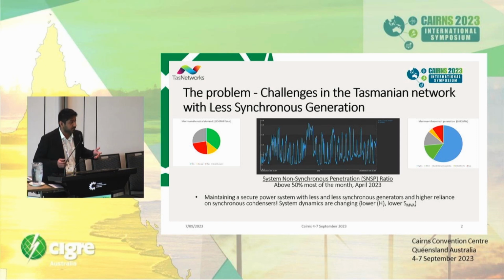So basically, if we encounter a fault, we need to see if a wind generator is injecting reactive current during that time, or whether it gets desynchronized from our network. So it's really important to get that visibility, and the high resolution data from PMUs gives us that visibility and helps our system performance team act accordingly. We have also seen incidents where distribution faults sent our wind farms into FRT, so it's critical to keep monitoring this using high resolution PMU data.